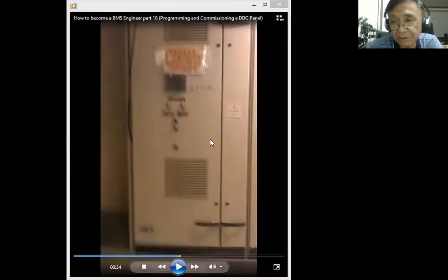As I said, this DDC controls and monitors the operation of the chilled water system. As you can see, I'm showing you one big MCC — a motor control center. Inside this motor control center is a big VFD that controls and varies the RPM of the chilled water pump. The VFD is used to change the speed of the motor, and changing the motor speed also changes the volume of chilled water it delivers.